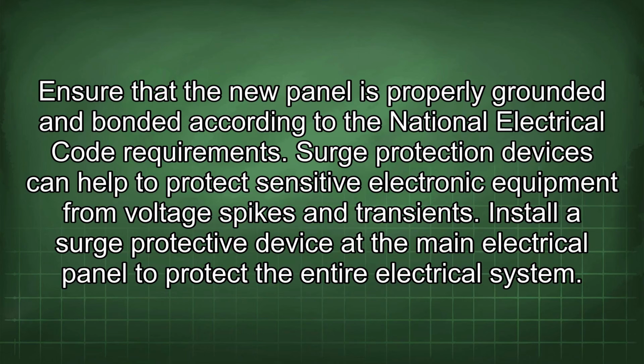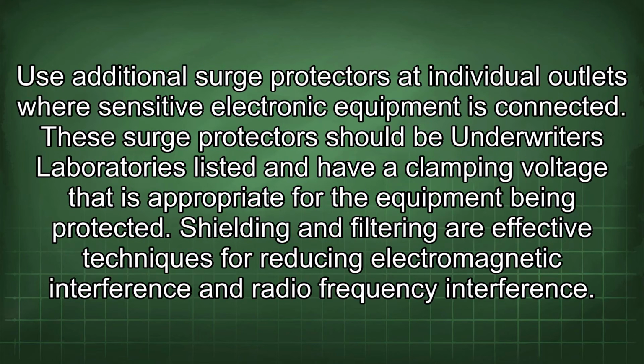Install a surge protective device at the main electrical panel to protect the entire electrical system. Use additional surge protectors at individual outlets where sensitive electronic equipment is connected. These surge protectors should be listed by Underwriters Laboratories and have a clamping voltage that is appropriate for the equipment being protected. Shielding and filtering are effective techniques for reducing electromagnetic interference and radio frequency interference.